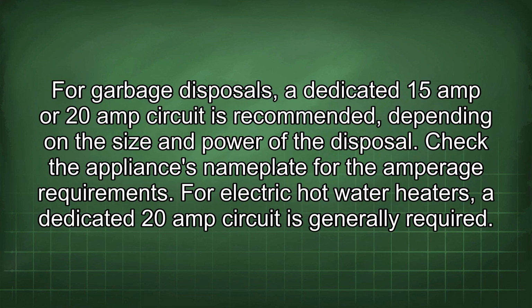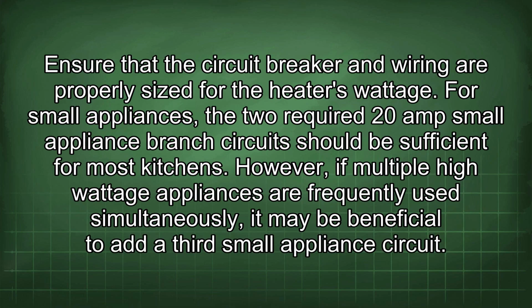For garbage disposals, a dedicated 15-amp or 20-amp circuit is recommended depending on the size and power of the disposal. Check the appliance's nameplate for the amperage requirements. For electric hot water heaters, a dedicated 20-amp circuit is generally required. Ensure that the circuit breaker and wiring are properly sized for the heater's wattage. For small appliances, the two required 20-amp small appliance branch circuits should be sufficient for most kitchens. However, if multiple high-wattage appliances are frequently used simultaneously, it may be beneficial to add a third small appliance circuit.